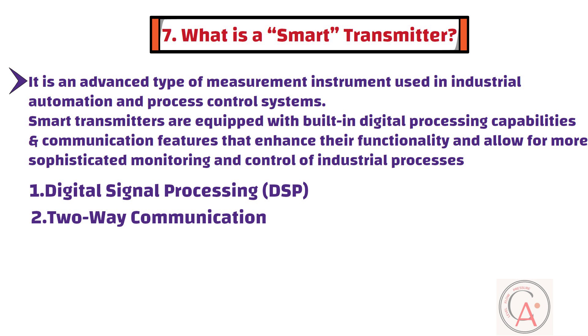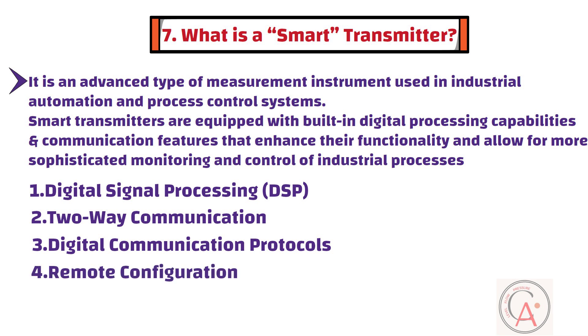Here are the key characteristics and features of smart transmitters. The first characteristic is digital signal processing, which allows them to perform complex calculations and signal conditioning tasks internally. The second characteristic is two-way communication with control systems and other devices. The third characteristic is digital communication protocols such as HART or Foundation Fieldbus. The fourth characteristic is remote configuration. The fifth characteristic is diagnostic information about sensor health, internal temperature, and potential issues or failures for predictive maintenance.